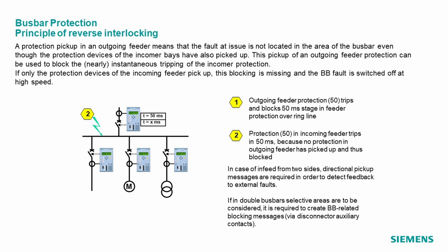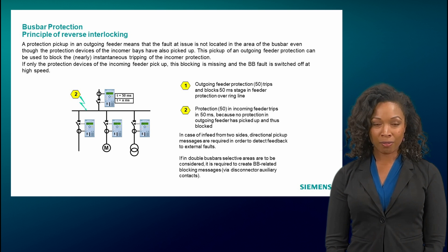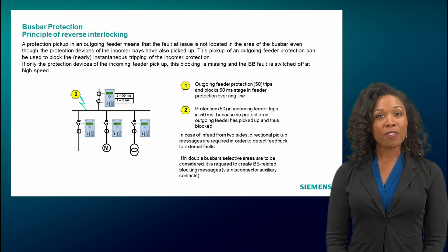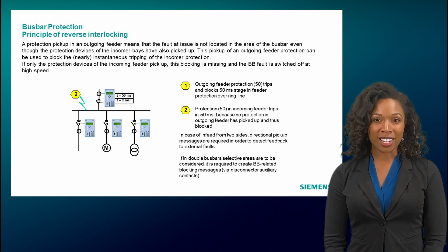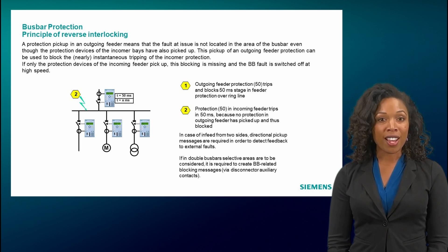Under the conditions described, the principle of reverse interlocking is a good and cost-effective solution as a busbar protection. However, if it is a switchgear with multiple busbar sections with longitudinal and transverse couplings, or if there is regenerative power via the outgoing feeders, or if a tripping time of 50 milliseconds is not sufficient, reverse interlocking becomes more complex. All these are aspects that may lead to using a busbar protection of type 7SS85 instead.